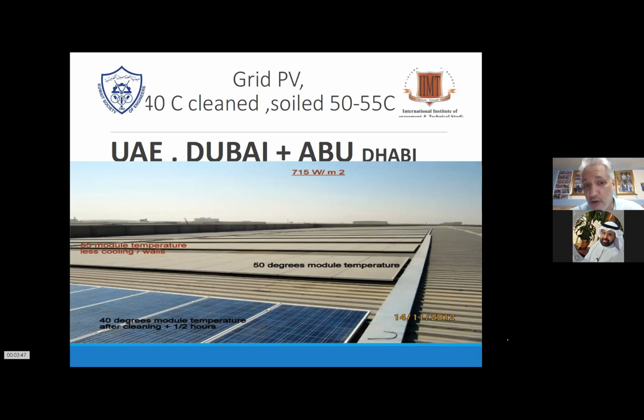That means they are below 600 or below 500, but the inverter is expecting between 600 and 580 mostly. Then it can go down further, and you can see the modules added on these serial strings are not enough. So they work in wintertime because they're cold and there's output, but in summertime, when they lose an additional 100 volt or 80 or 50, depending on your system, you always have to think back: who installed the system, who maintained the system, and are the connectors good?